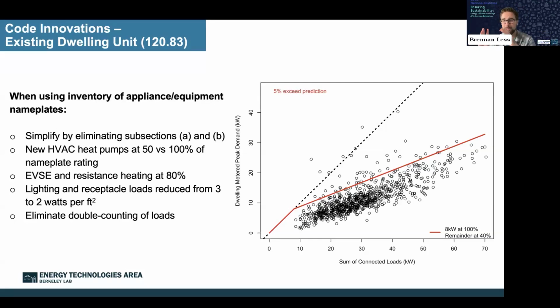We're simplifying it by eliminating the separate treatment currently in there for adding new HVAC equipment. That means we'll be able to add new HVAC heat pumps to homes at a 50% rating versus 100% of their nameplate - essentially doubling the amount of heat pump we might be able to add to a home. A really big effective change.